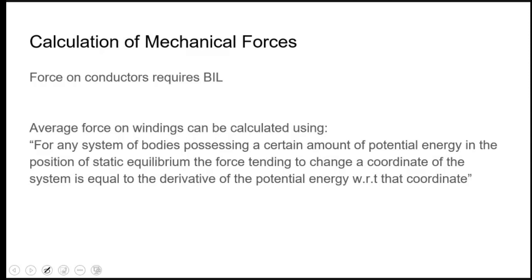Yes, that is true. If you want forces on individual turns, there are two things here. If we know the forces on the winding as a whole, for example the primary winding and secondary winding, then this can be useful for the design of spacers between the windings, and between winding and core also.